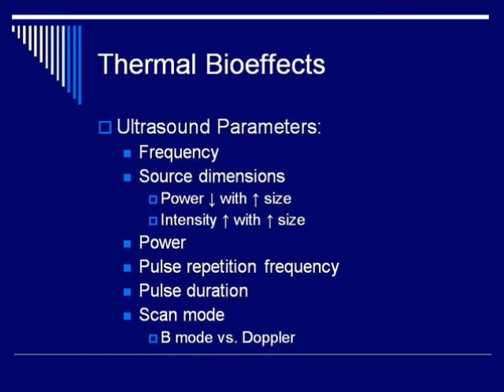Power, I think, is relatively straightforward — more power, more heating. Pulse repetition frequency, which is how often the ultrasound is pulsing: increased pulse repetition means more pulses, equals more exposure, equals more heating. Pulse duration works the same way — the longer the pulse is, the more exposure you get. And finally, the scan mode you're in really affects the amount of bio-effects you can get. If you're in a scanning mode such as B mode, you will have relatively low exposure compared to power Doppler or spectral Doppler, which involve large amounts of ultrasound going into a small area — the area that you're checking out with Doppler specifically.